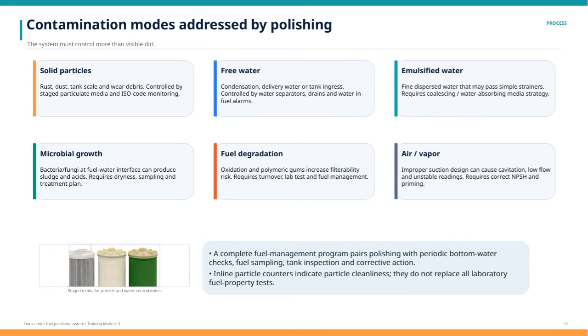Fuel degradation, caused by oxidation and the formation of polymeric gums, increases the risk of filter clogging. Managing this involves fuel turnover, lab testing, and an overall fuel management strategy. Lastly, air and vapor issues, often due to improper suction design, can lead to cavitation, low flow, and unstable sensor readings. These problems require the correct net positive suction head, or NPSH, and proper priming techniques.